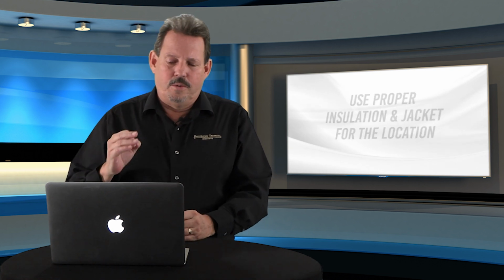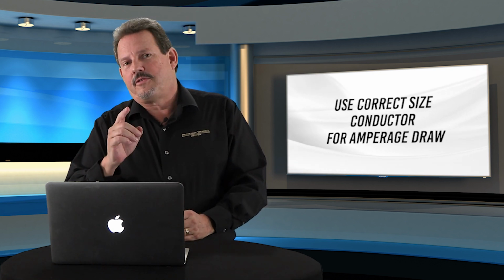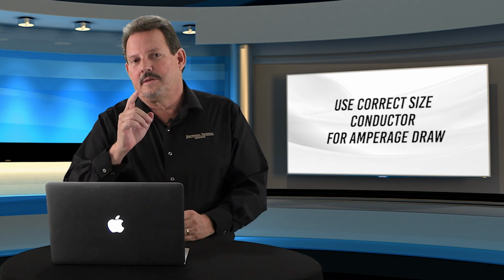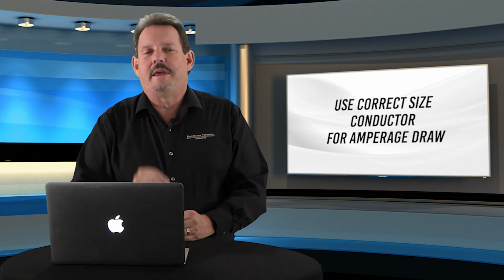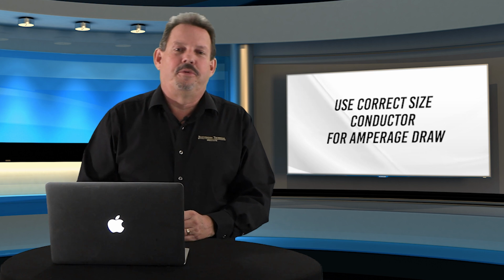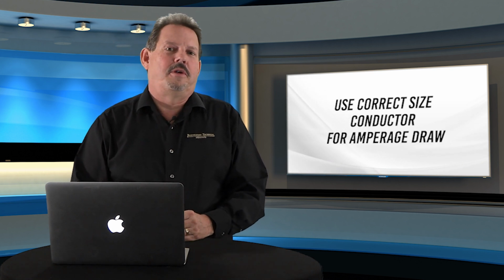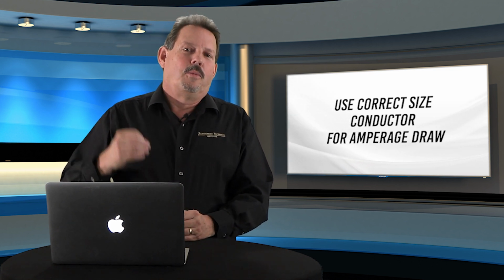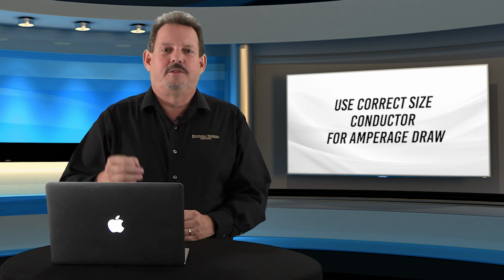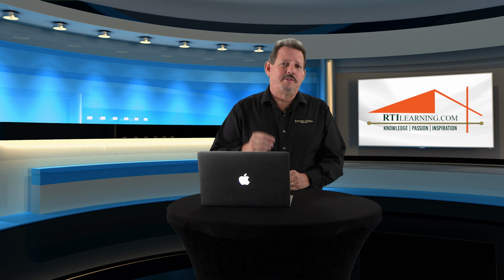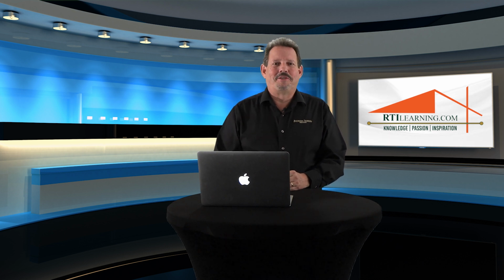Always make sure the conductor is correctly sized for the amperage draw. If you're going to put 12 amps on an extension cord, make absolutely sure you have a 15 amp extension cord with the proper gauge conductor or wire inside of it so that it will continually carry those 12 amps without a problem. If you have more questions on extension cords, see our other episode, The Do's and Don'ts of Extension Cords.